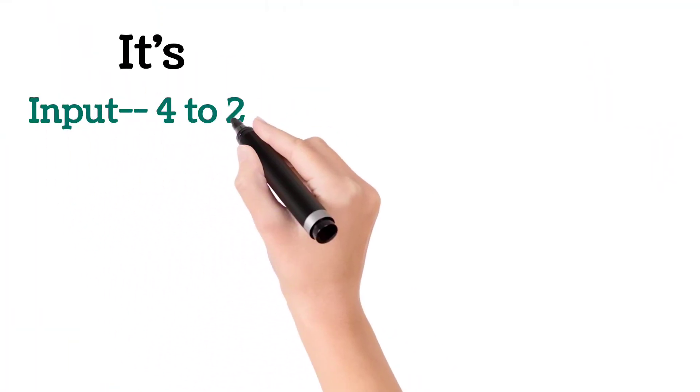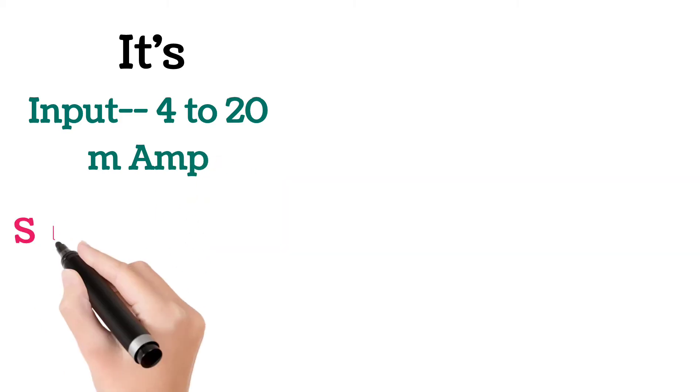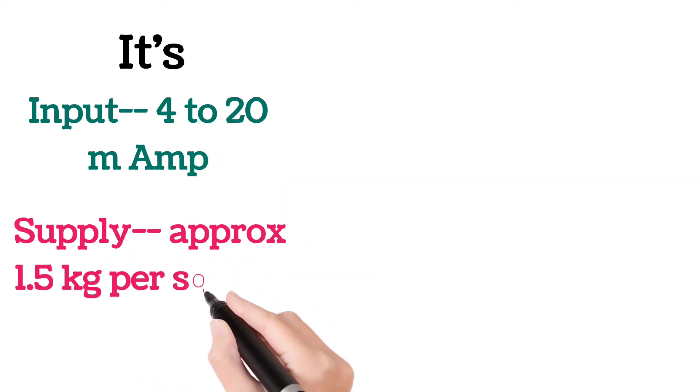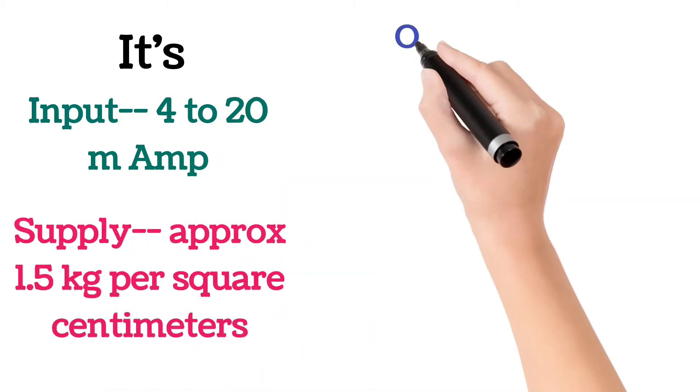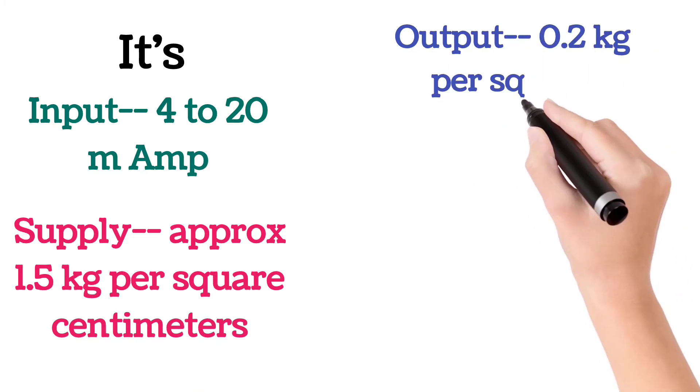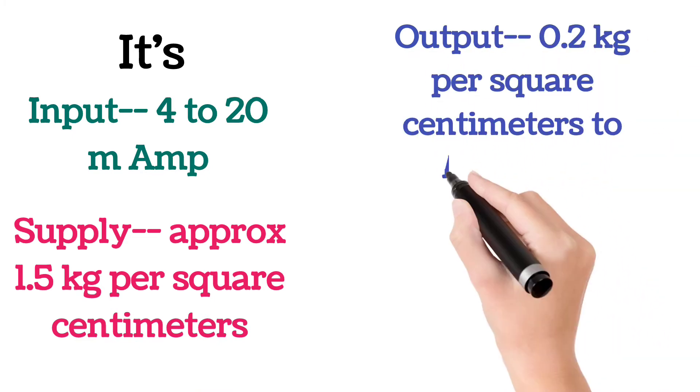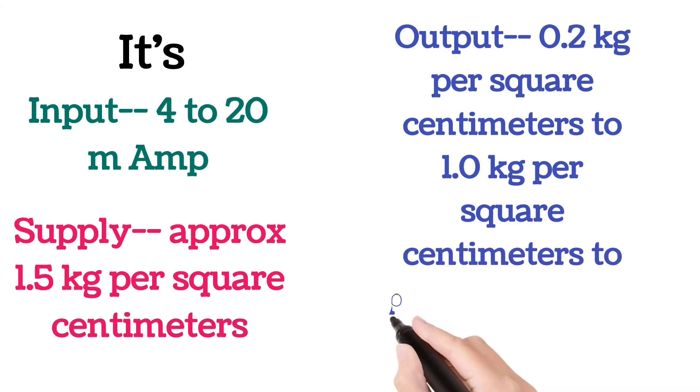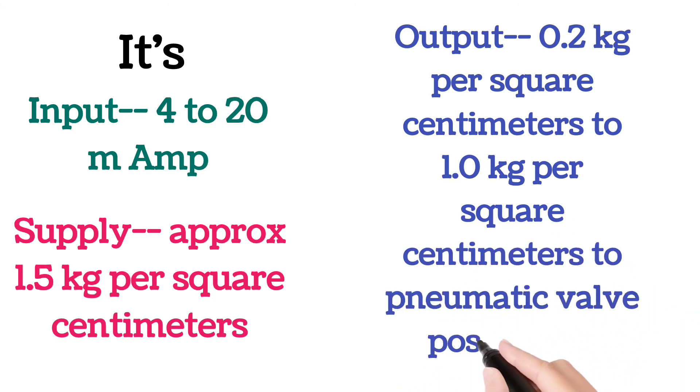I to P converter input is 4 to 20 milliamps. Its supply is approximately 1.5 kg per square centimeter. And its output is 0.2 kg per square centimeter to 1.0 kg per square centimeter and is provided to pneumatic valve positioner.